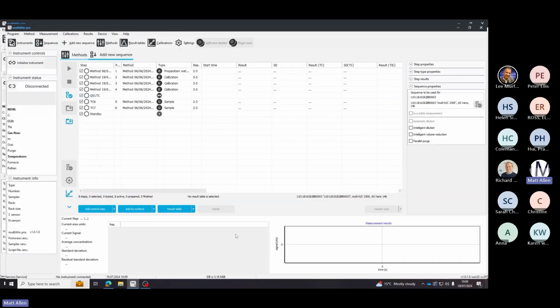Okay, so we're going to look at some extra software features within MultiWin Pro. Just over to the right hand side in the step properties, you can see we've got intelligent dilution, intelligent volume reduction, parallel purge. So intelligent dilution and intelligent volume reduction do similar things, which is that if your sample is getting close to or exceeds the calibration range, it will then perform a dilution, or it will reduce the sample volume. So really good for unknown samples.